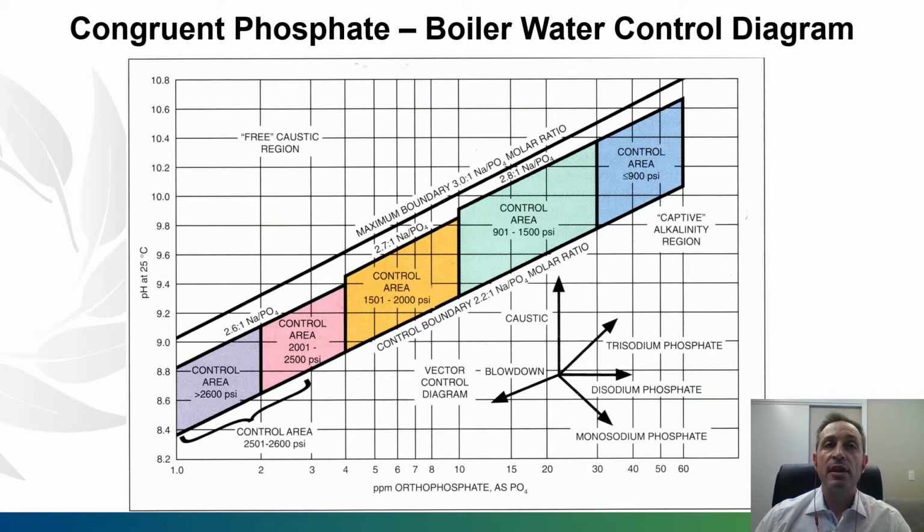And the concept is that if you are able to provide that, you will minimize many different corrosion processes, phenomena in the boiler. Of course, other variables can change, but this is very important and must be kept between the box. This is why many people say in-box time or controlled time in the box for a given phosphate residue and a pH.